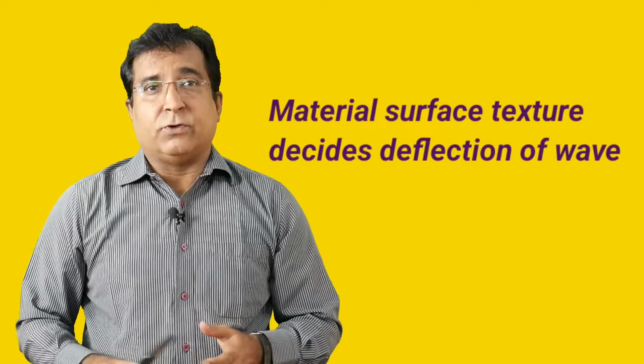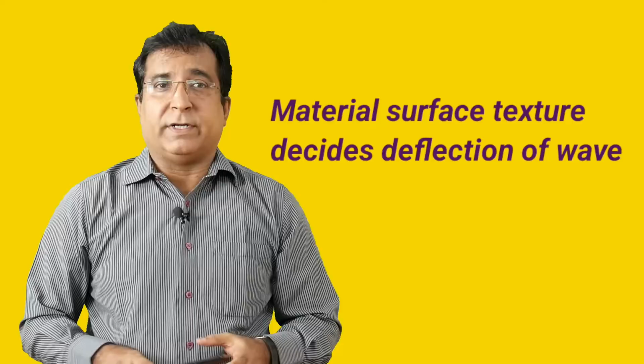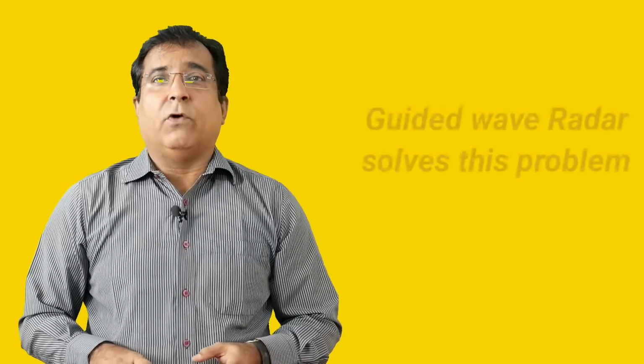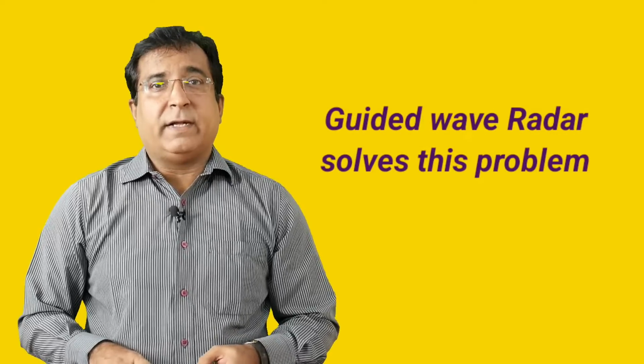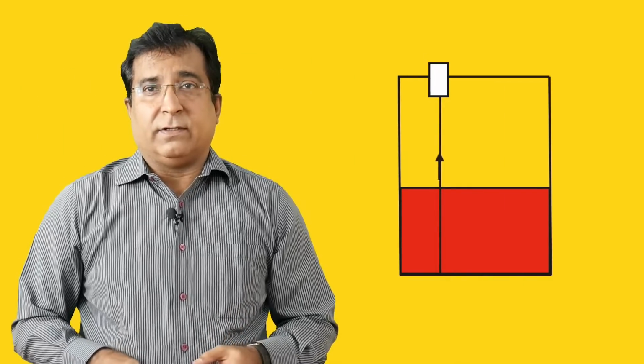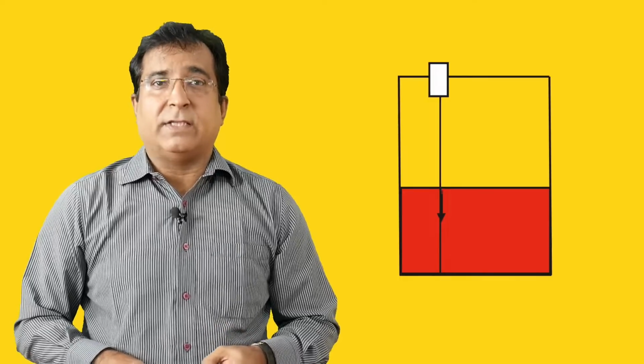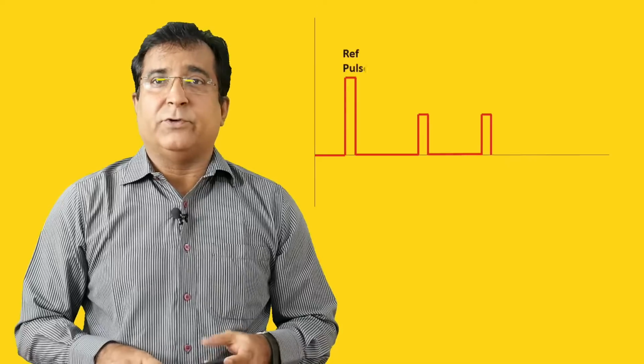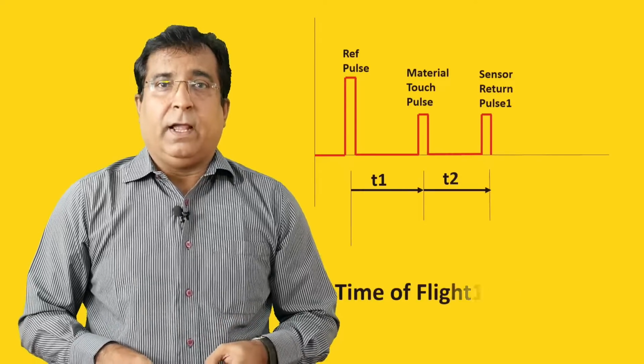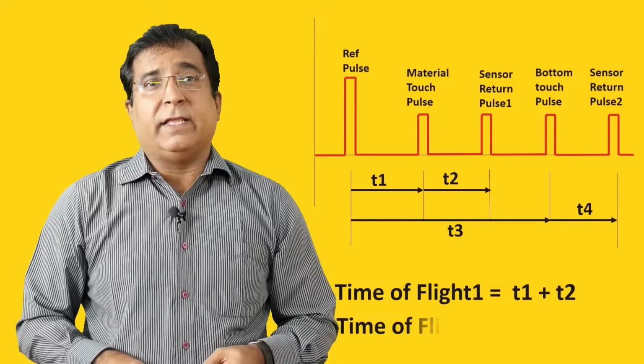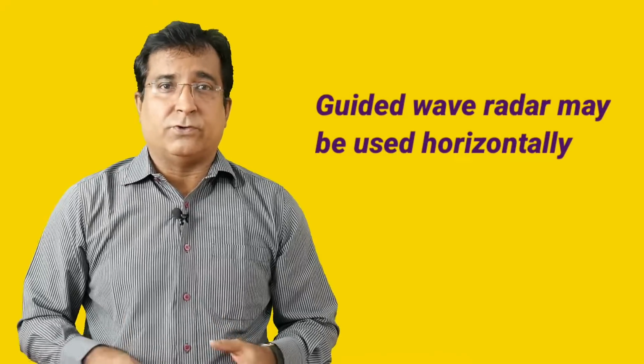Both techniques face beam diversion issues due to an uneven or turbulent surface of the material. To resolve this, one may go for a guided wave radar system. Here a metal rod acts as a probe which guides the wave to the bottom of the tank or hopper. Guided wave radar is more efficient than through-air radar systems, as the electromagnetic wave's energy is channeled in a straight line over a probe, while antenna type radar suffers much more signal loss due to dispersion of electromagnetic radiation. It can be used horizontally as well, and all the beam diversion issues and false echo issues are resolved here.